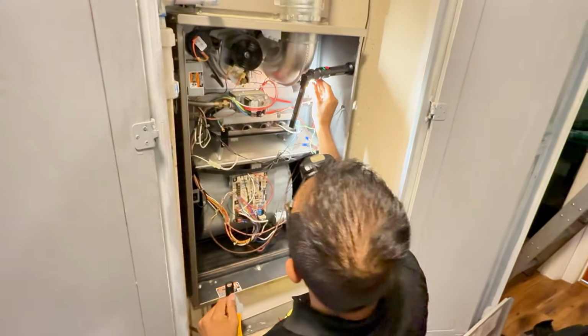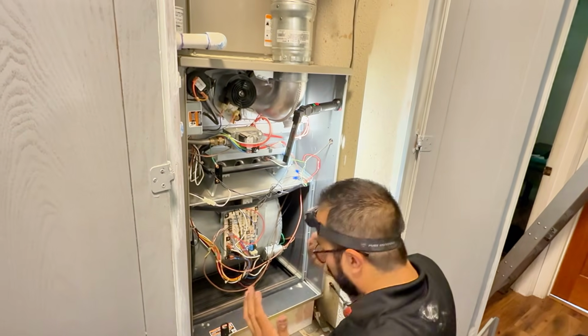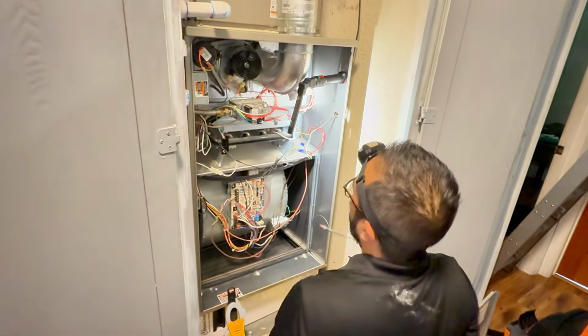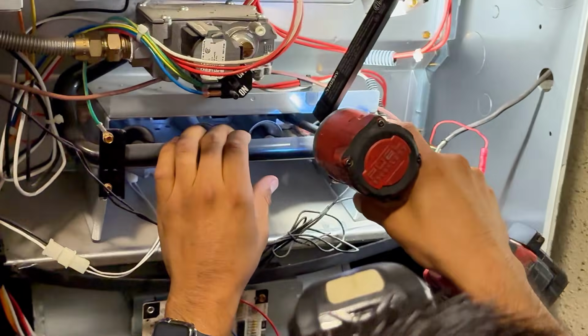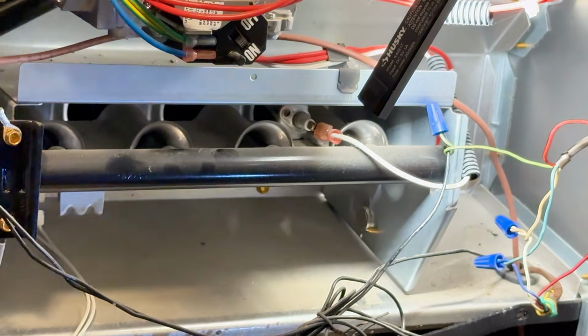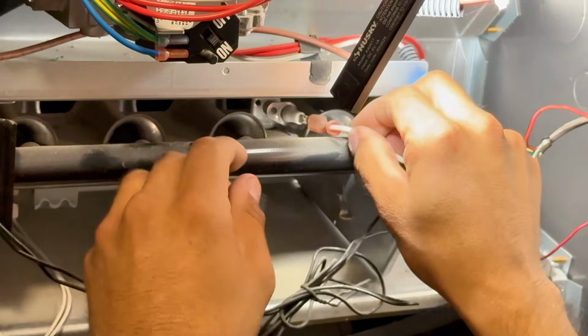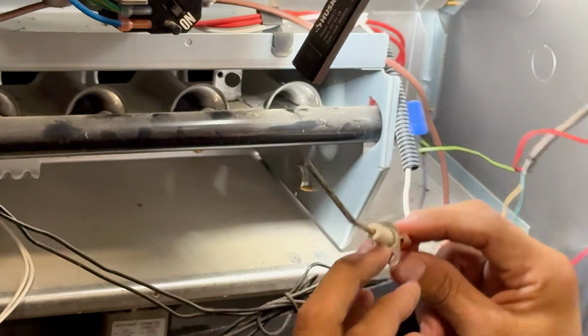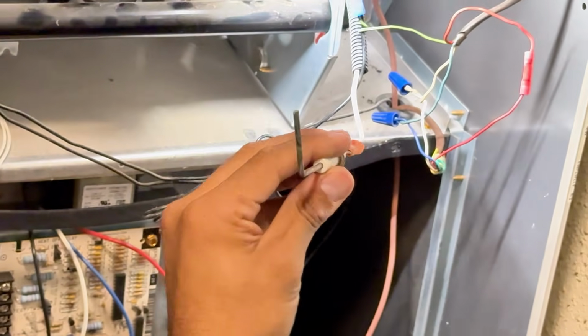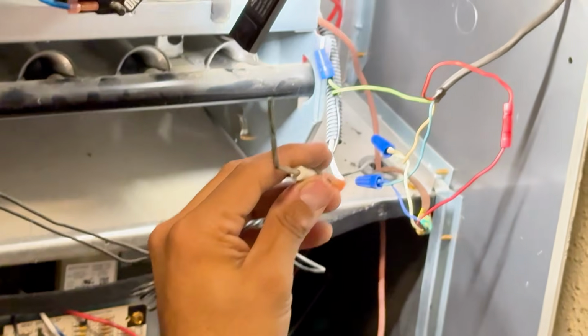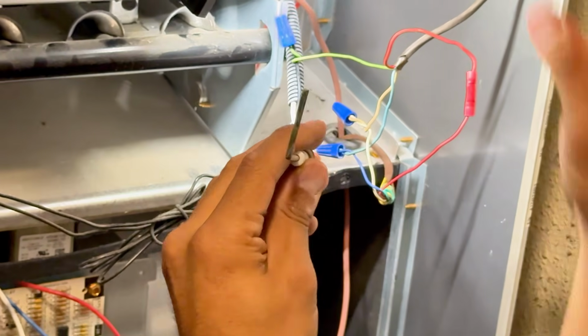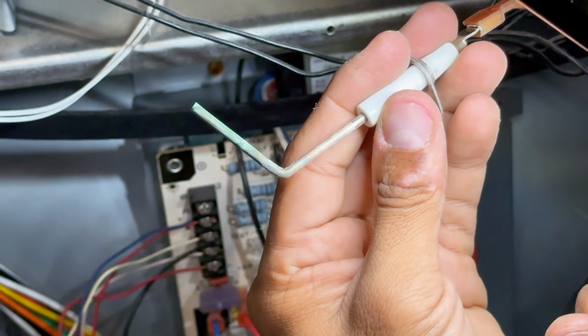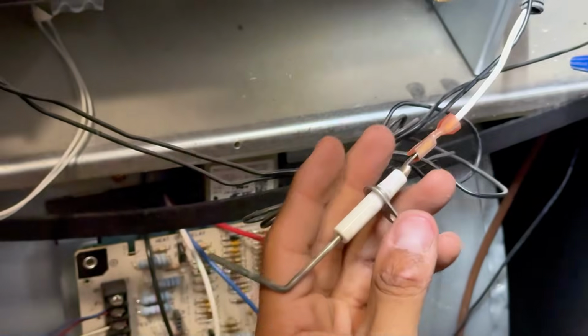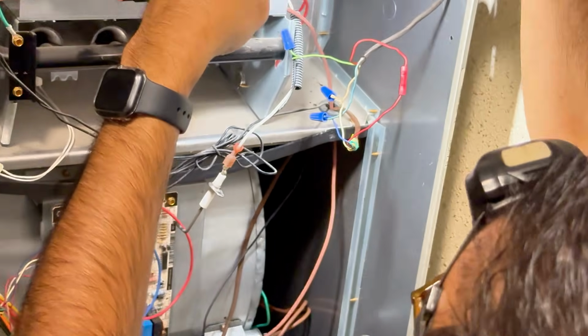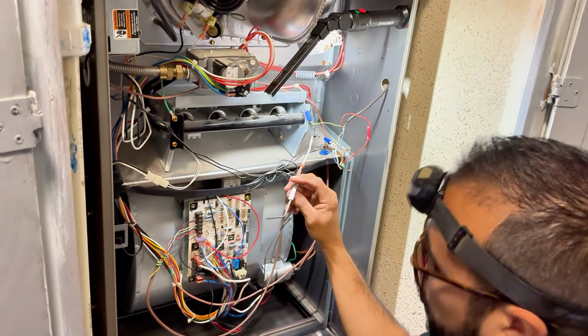So one more thing, this is a furnace, so you're supposed to remove the flame sensor and then clean it. Do not use sandpaper. You see, let's get a close up of this. Where's my light? Oh you see right there? That's dirty, that is dirty right there. So we're gonna use either steel wool, or if you have a dollar bill, you can use that too.